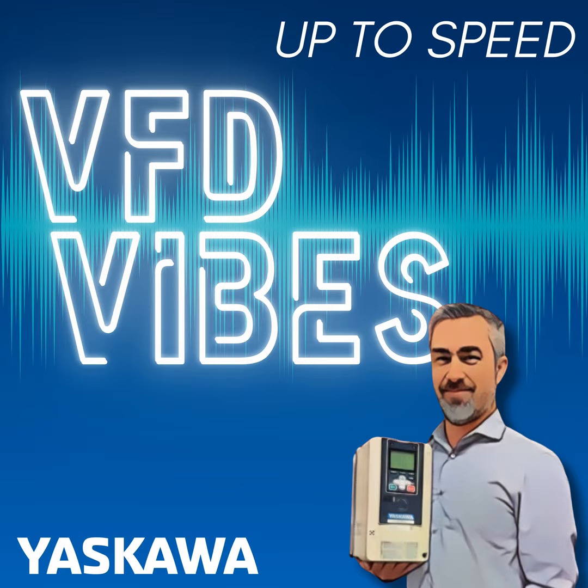Can you keep going with some other common parameters? Sure. Yeah. So on a startup, and especially a fan or pump, and I probably tend to focus on HVAC applications because that's what I do in our group now for the last 9 years. And that was my primary focus in tech support as well. But one of the things I always had the techs change when I was doing a call in tech support, and often I'd get calls in tech support where the service tech would say, "Hey, I'm starting this drive up. What do I need to do?" And they wouldn't even know what they needed to run at, what speed. I'd ask them, okay, how are we sending a run command speed reference? We'd go through some of these basics. I'd get them up and running. Maybe I'd recommend a minimum speed.